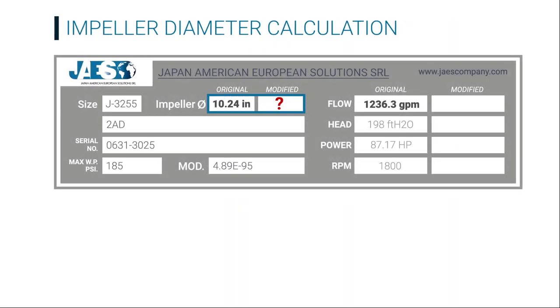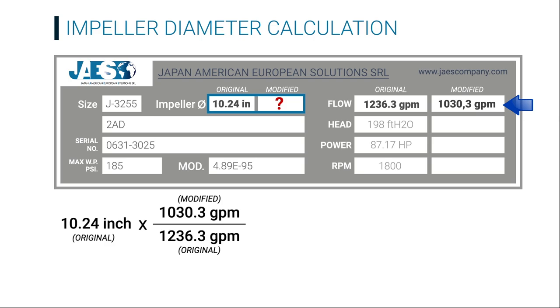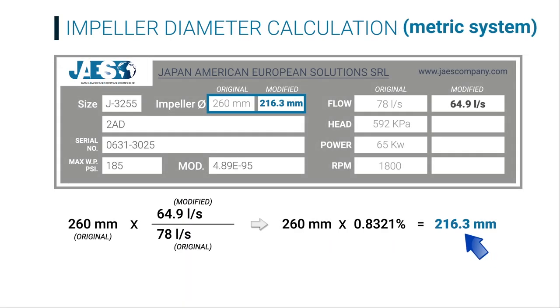In conclusion, we are going to calculate the pump impeller diameter. How much should the impeller diameter measure if we want to reach the modified flow rate value of 1030.3 GPM? This calculation is used in the case where the impeller is actually trimmed down to meet the new flow rate. We cancel out the GPM of this division to find the ratio, which we multiply by the original impeller diameter — 10.24 inches — to find 8.53 inches, or 216.3 millimeters.